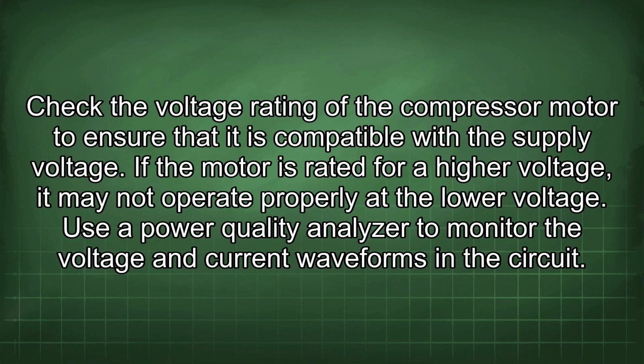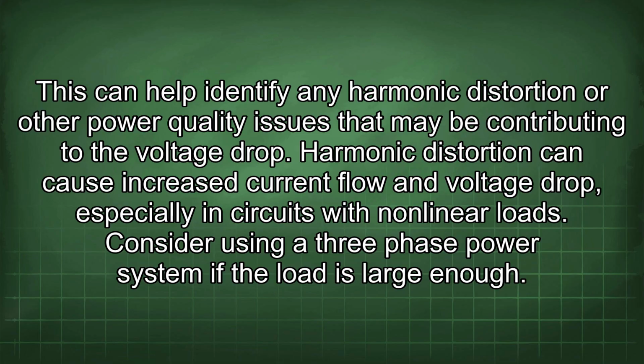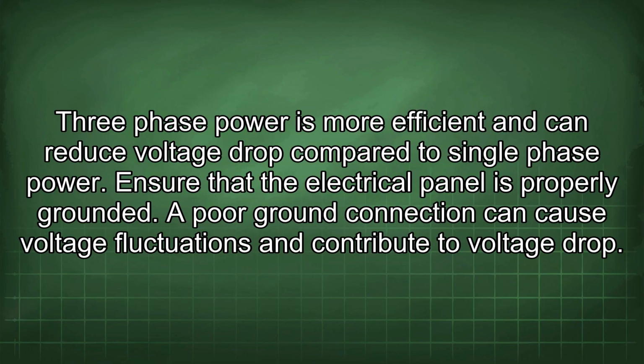Use a power quality analyzer to monitor the voltage and current waveforms in the circuit. This can help identify any harmonic distortion or other power quality issues that may be contributing to the voltage drop. Harmonic distortion can cause increased current flow and voltage drop, especially in circuits with nonlinear loads. Consider using a three-phase power system if the load is large enough. Three-phase power is more efficient and can reduce voltage drop compared to single-phase power.